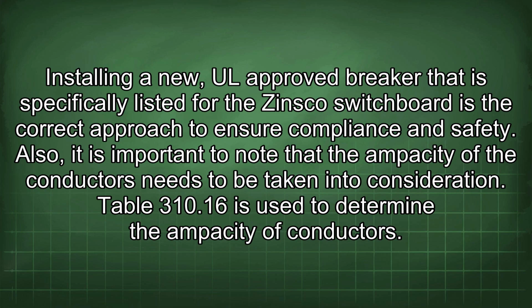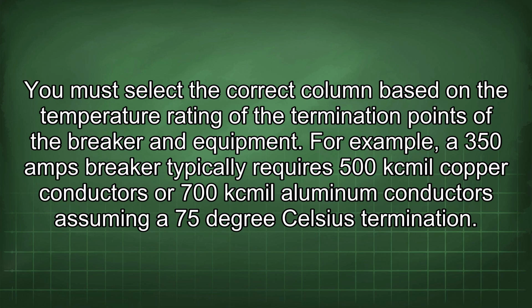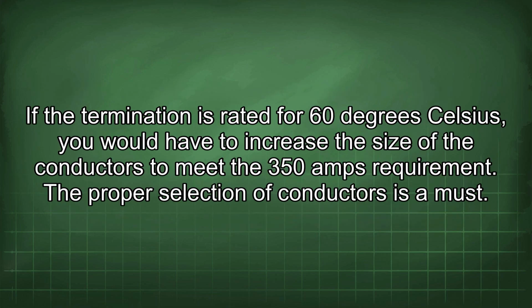Also, it is important to note that the ampacity of the conductors needs to be taken into consideration. Table 310.16 is used to determine the ampacity of conductors. You must select the correct column based on the temperature rating of the termination points of the breaker and equipment. For example, a 350 amps breaker typically requires 500 kcmil copper conductors or 700 kcmil aluminum conductors, assuming a 75 degrees Celsius termination. If the termination is rated for 60 degrees Celsius, you would have to increase the size of the conductors to meet the 350 amps requirement. The proper selection of conductors is a must.